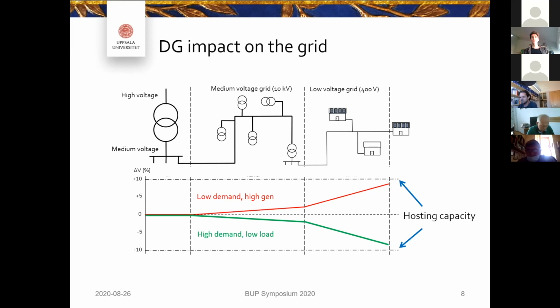What we did is referred to as the hosting capacity of the grid. We've seen in many previous studies that overvoltage, when it comes to PV, is the most crucial parameter. There are of course other measures such as current, which is also quite important. For wind power, harmonics has been one issue in some cases, but for solar it's mostly the overvoltage issue that limits PV deployment into the grid.